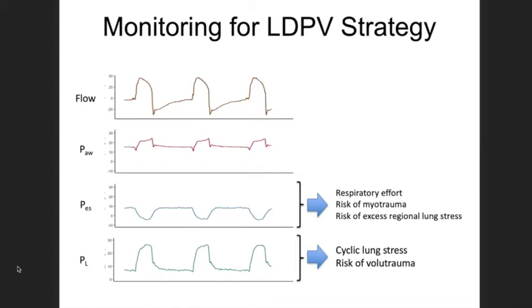So when you have a balloon in place, you can see that the flow and the pressure being applied by the ventilator here are also resulting from inspiratory efforts from the patient, and you can quantify these swings in transpulmonary pressure in real time on the ventilator. There are several ventilators now that allow you to monitor transpulmonary pressure with the balloon in real time. And so these measurements provide very useful information.